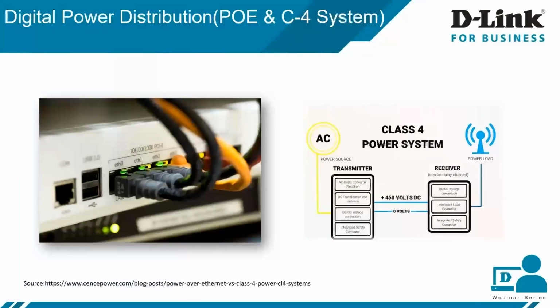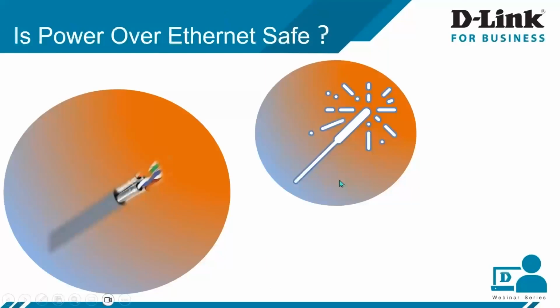Conversely, the power load does not need to be specifically class 4 enabled, whereas in PoE we knew both devices should be PoE enabled for it to work. The class 4 system has a power receiver that converts class 4 power back to the required voltage. Again, similar to PoE, class 4 systems typically only require low voltage wiring practice. So these are the differences between PoE and class 4 DC power distribution system.